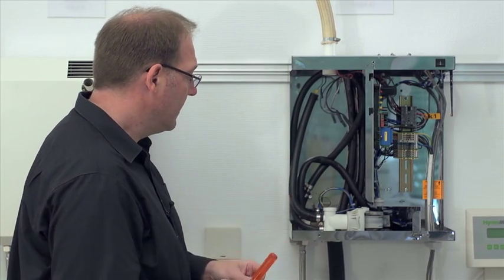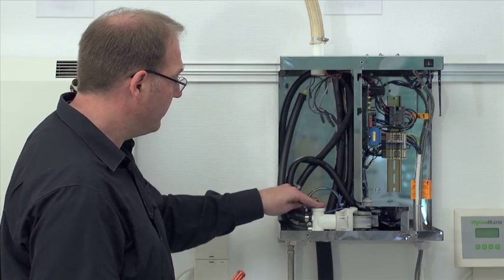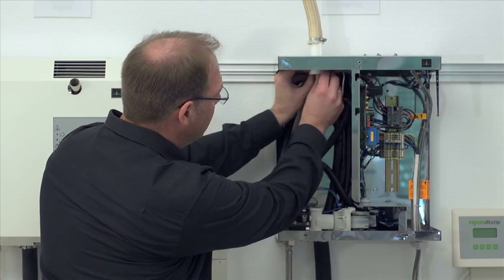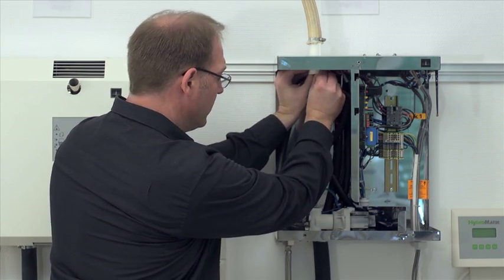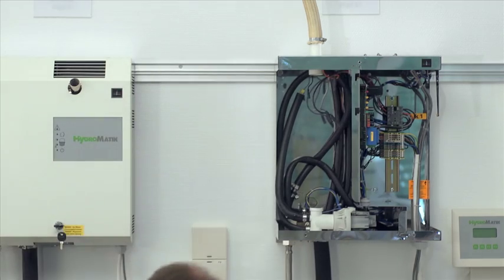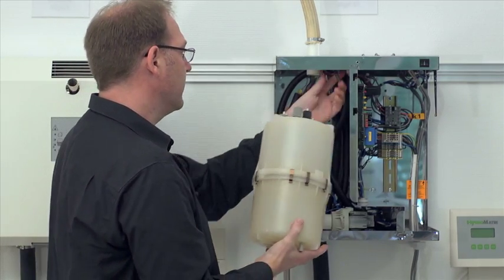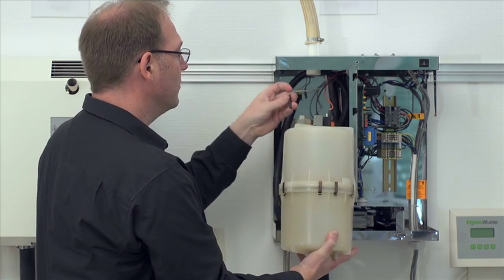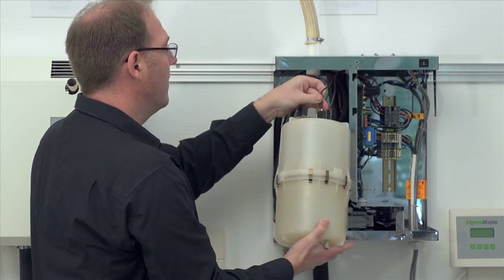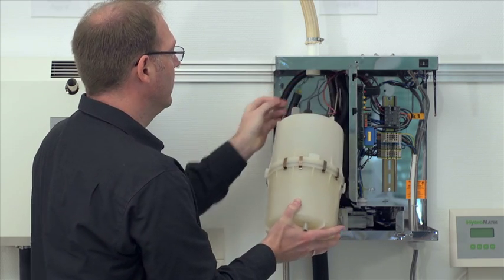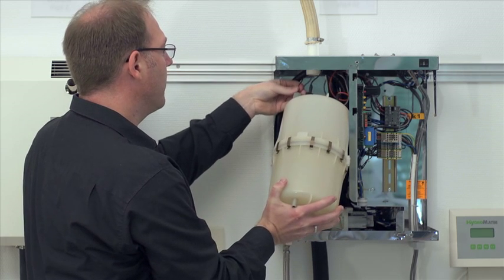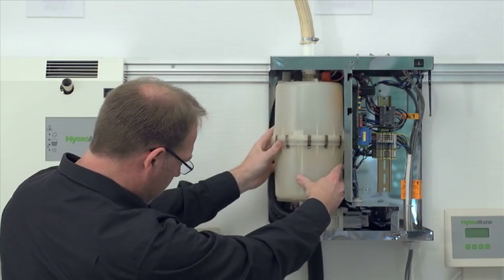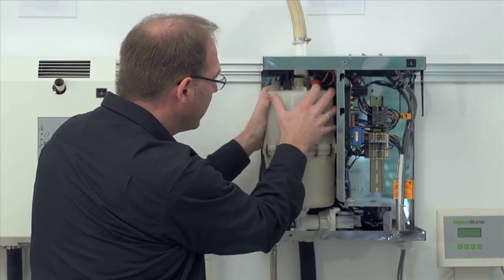If that's okay so far, I insert new o-rings, one o-ring down in the base and another new one goes up on top in the steam hose adapter. I place it up in the groove, and then I can actually hook the steam cylinder back up to the power supply that is on top. The electrode connection plugs are attached, and then here the small sensor electrode, and then I place the cylinder into the base.